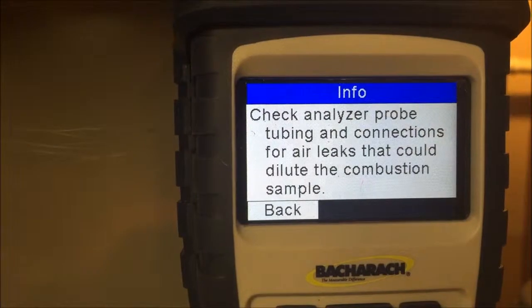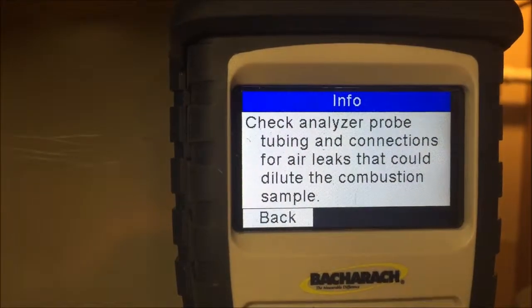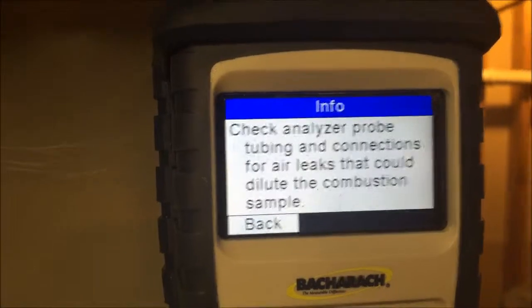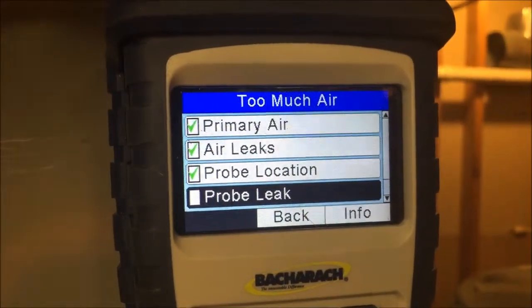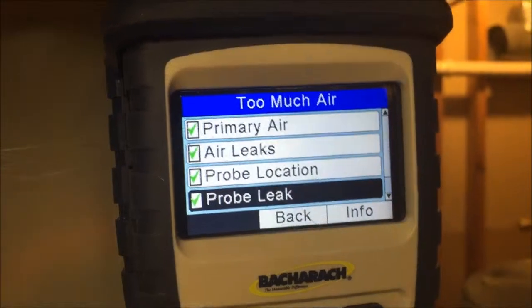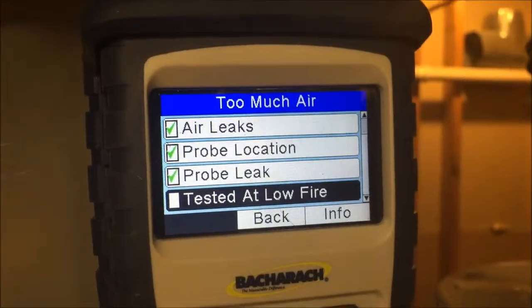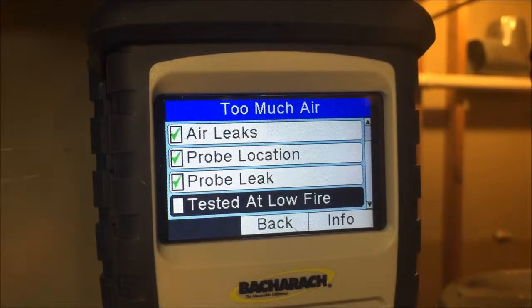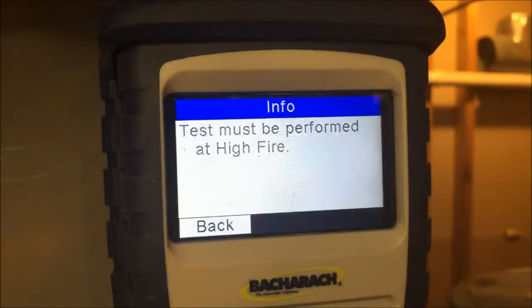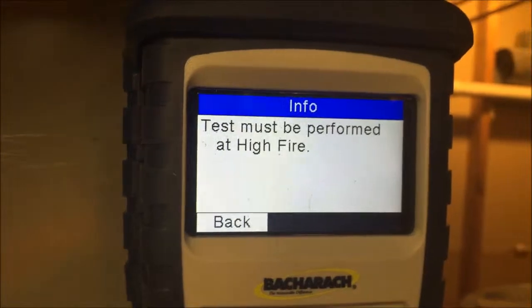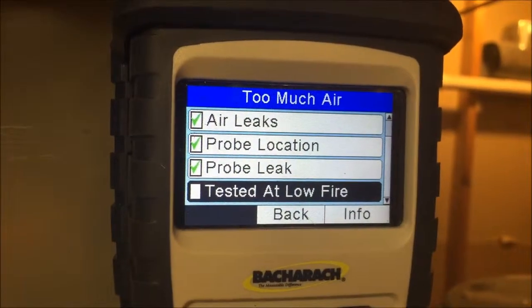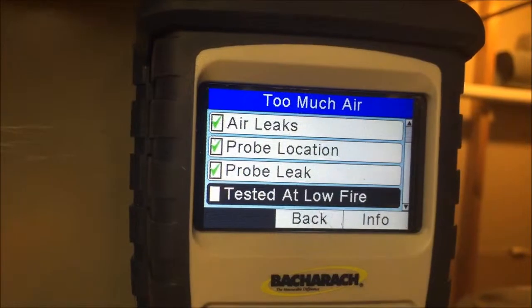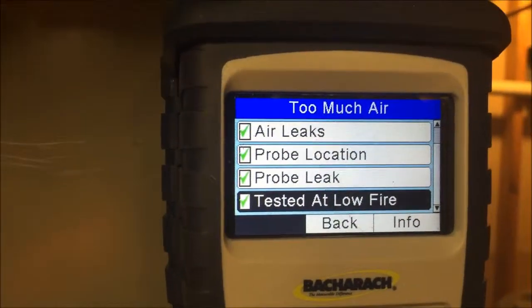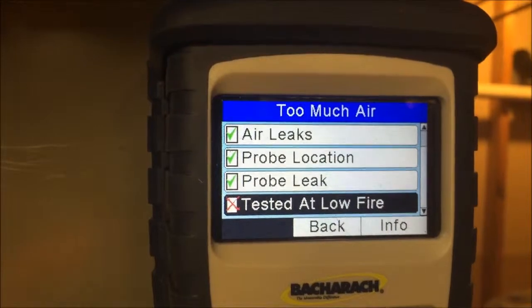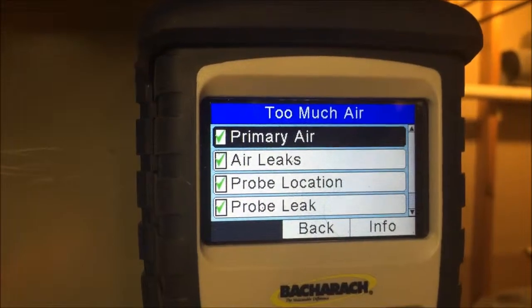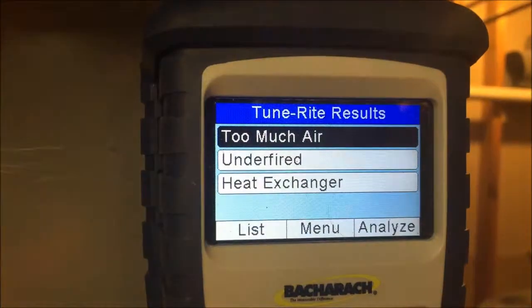What about a probe leak? Check the tubing, make sure it doesn't have a leak. Make sure it's not cracked, drawing in air with the pump. Nope, the probe is good, the tubing is good, it's not an issue. Still got room. Test it at low fire. Test must be performed at high fire. Well, you know what? I did test it at low fire, so I'm going to check that. I did do that. That's the wrong thing. So that's what was wrong.